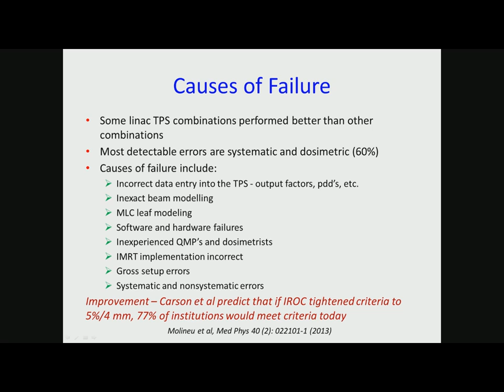So IROC is trying to decrease that threshold from 7% to 5% and to 4 millimeters. So they looked at that, if they had changed the tolerance to this tighter tolerance, now 77% of institutions will meet the criteria today. And that's not good, that's almost 24% of them failing the criteria with the tighter spec.